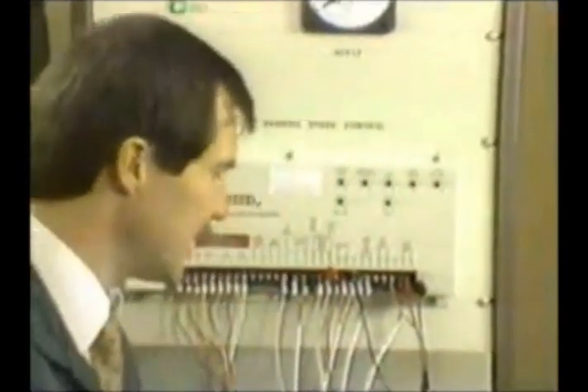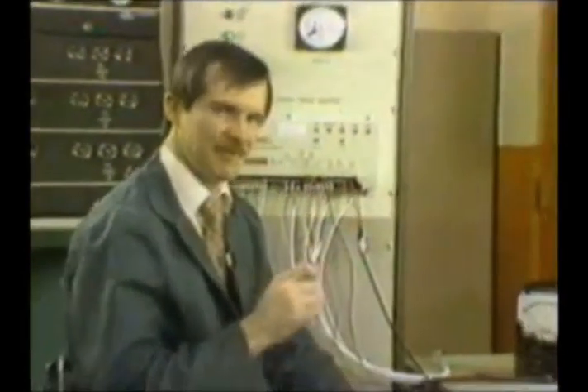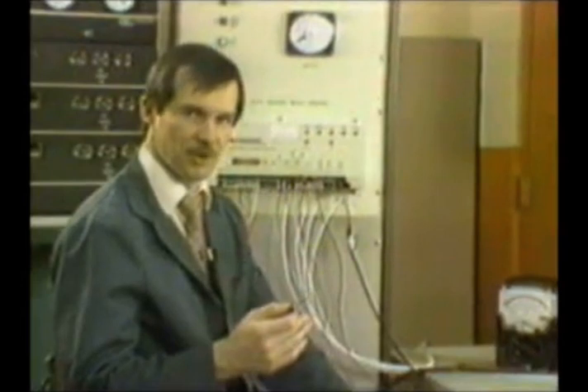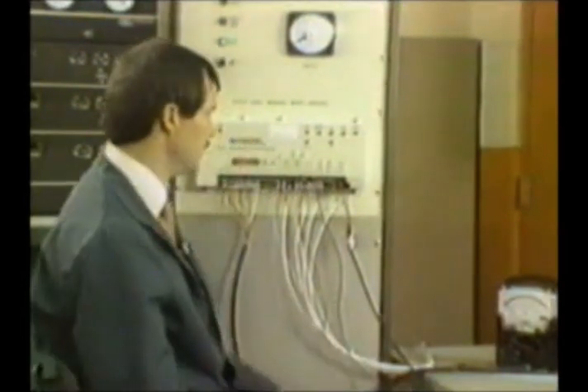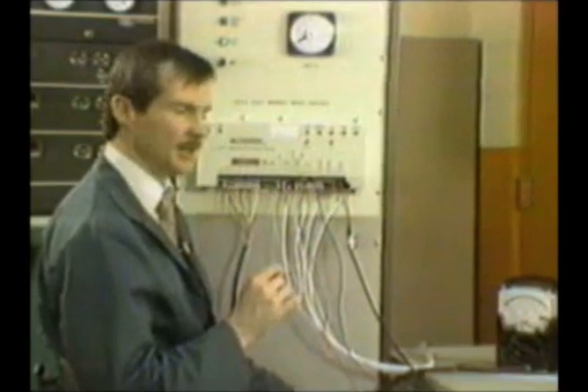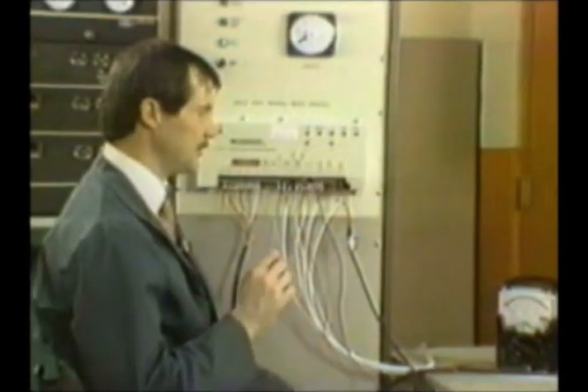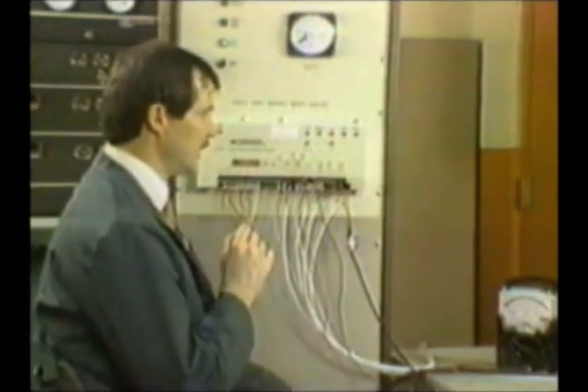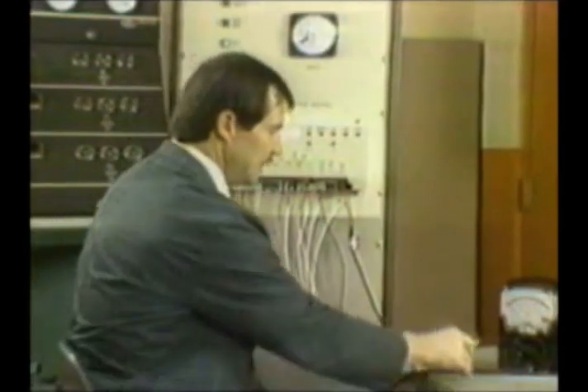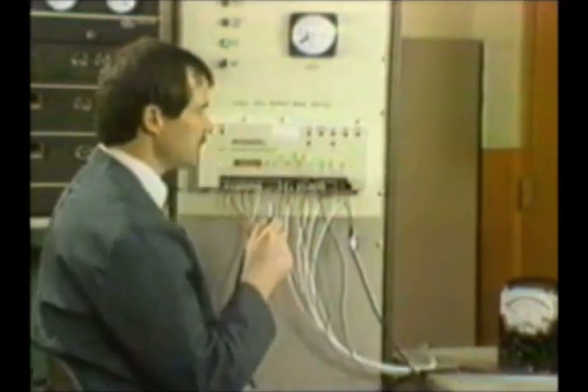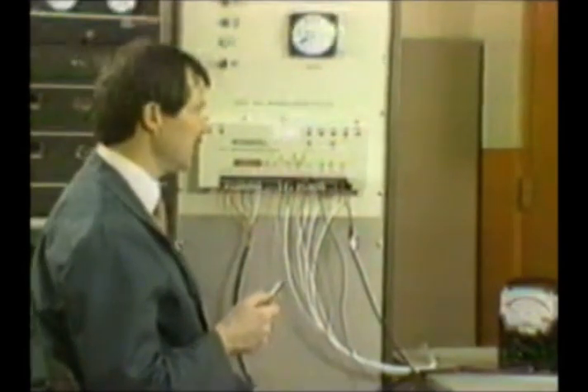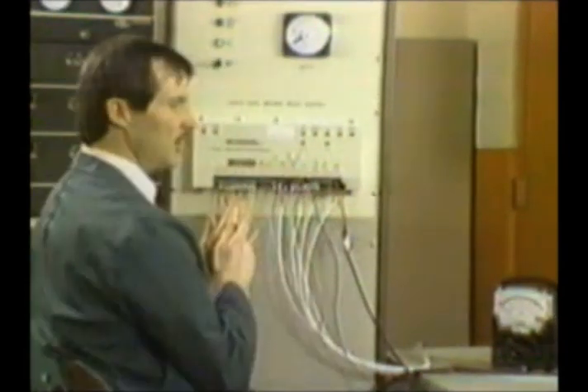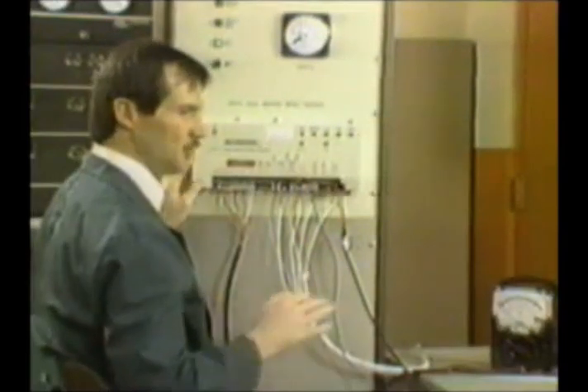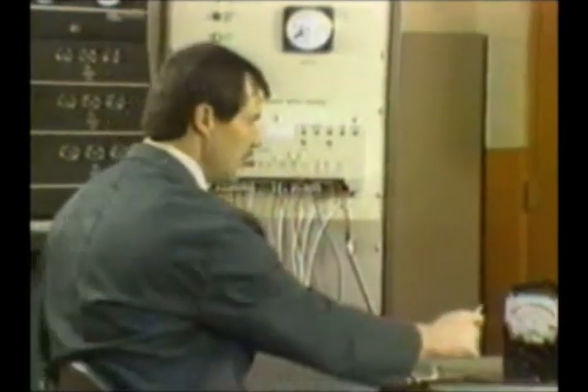Now that we're feeding that signal in, you need to make sure on your function generator that you have your output level above 1 volt RMS. So make sure you don't have your output level turned fully counterclockwise on the function generator. Now what you're going to be looking at here is your analog meter, and as I turn the rated speed pot clockwise, as we hit the point that the 2301A wants to control at 4680, our actuator voltage will integrate high.